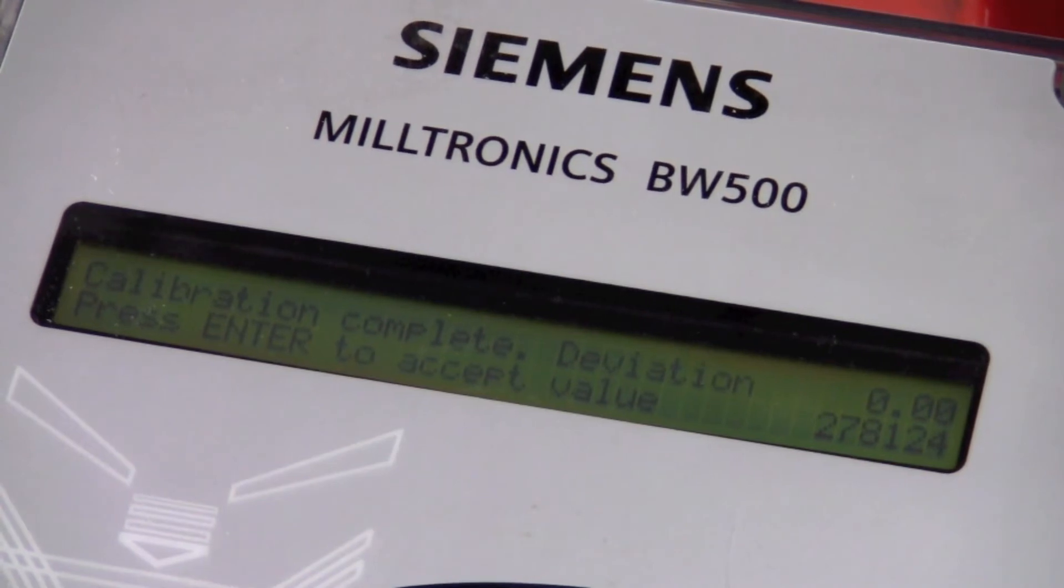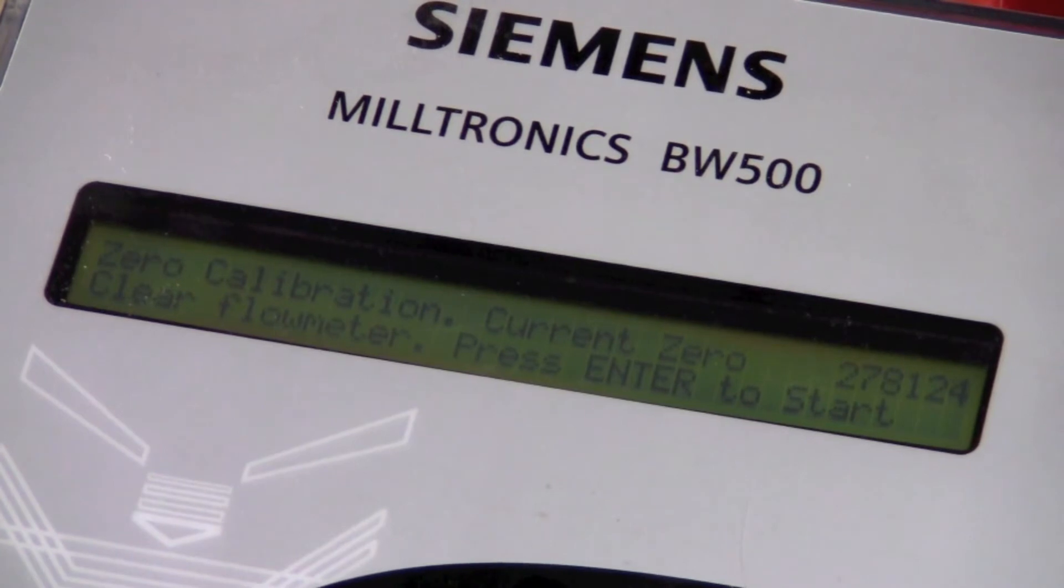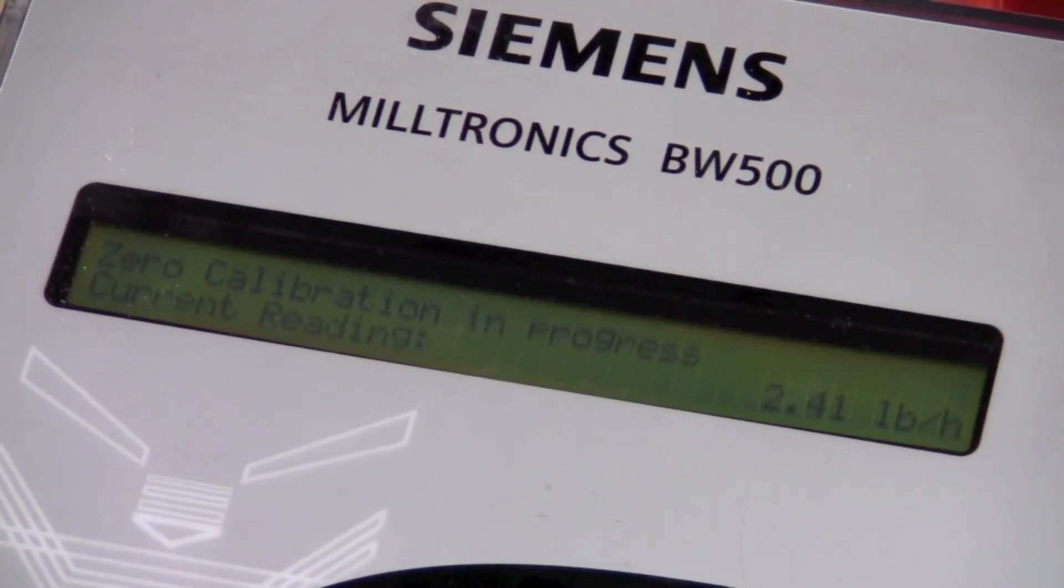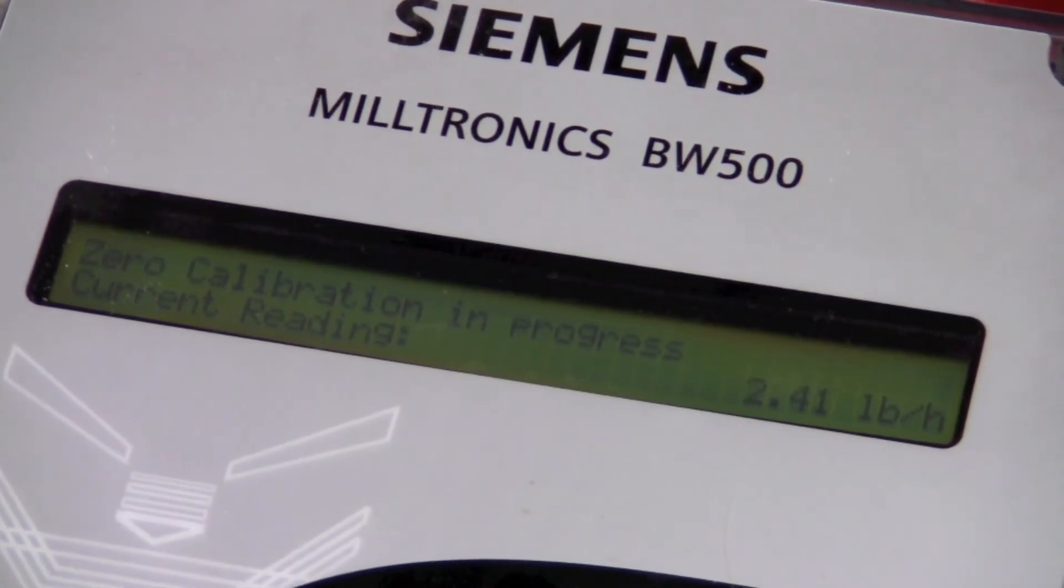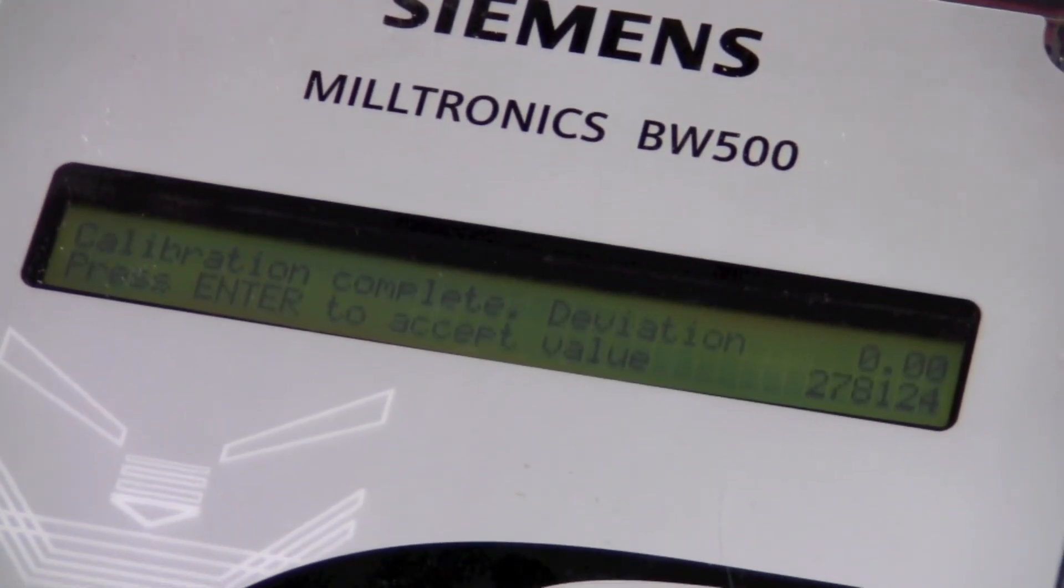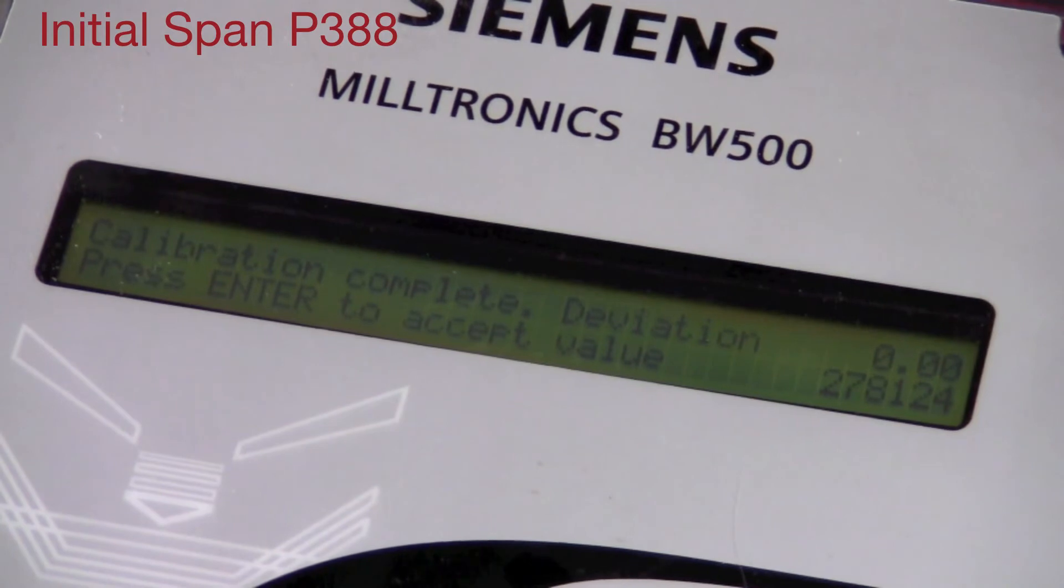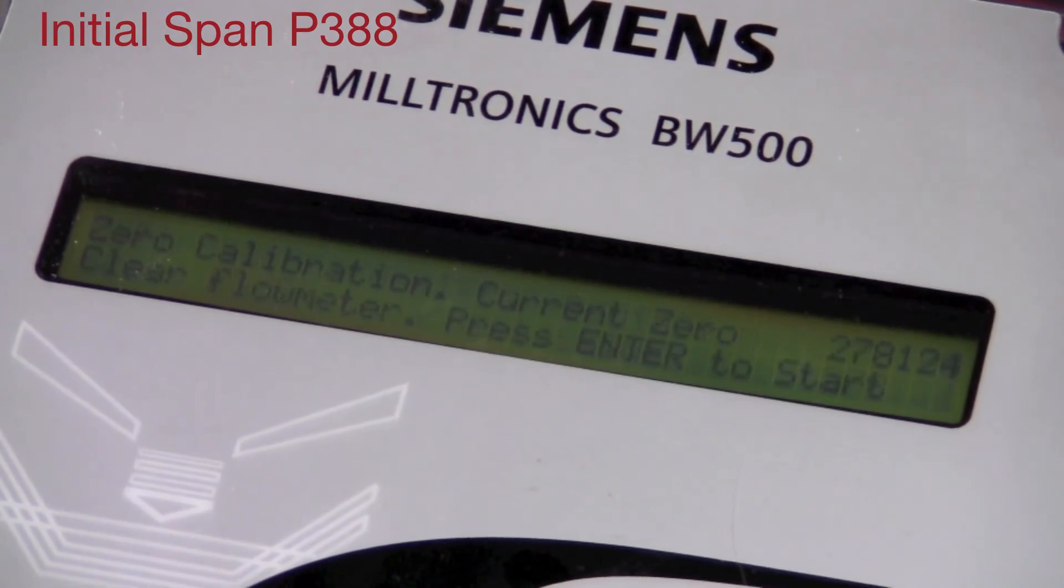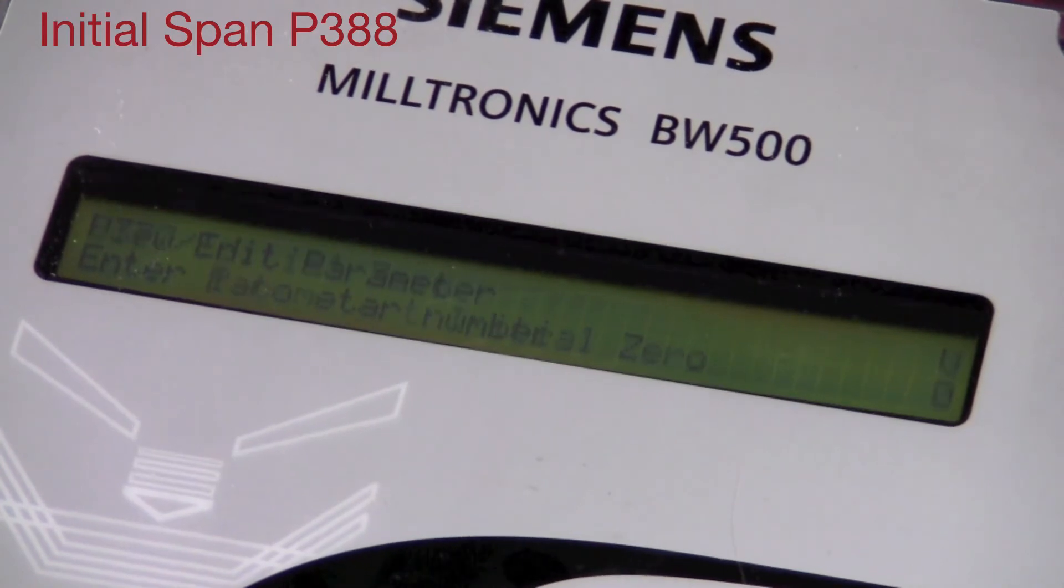We'll accept this value and do a second zero to see if there's any deviation. The deviation is minimal, actually zero, so we're ready to do an initial span, which is parameter 388.